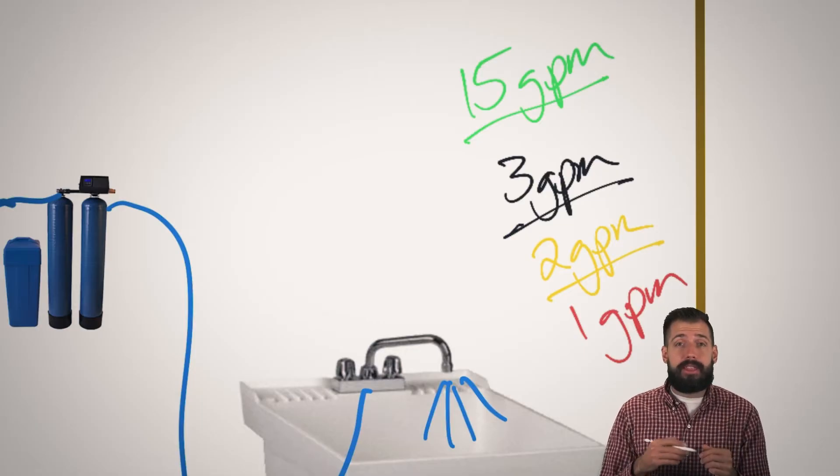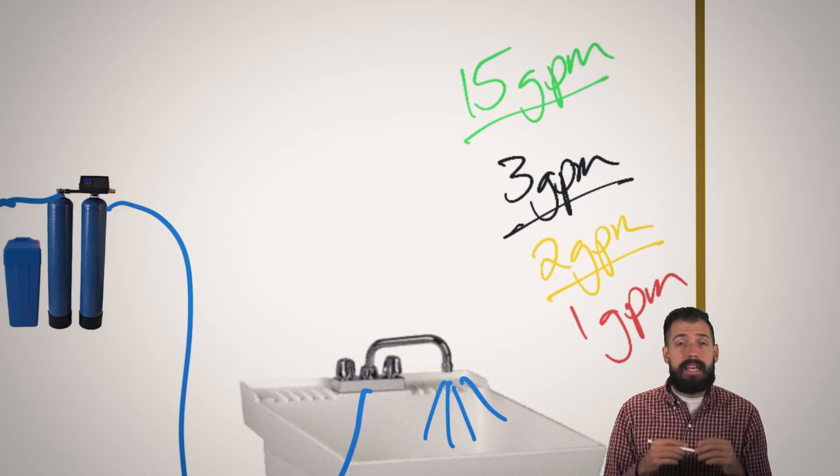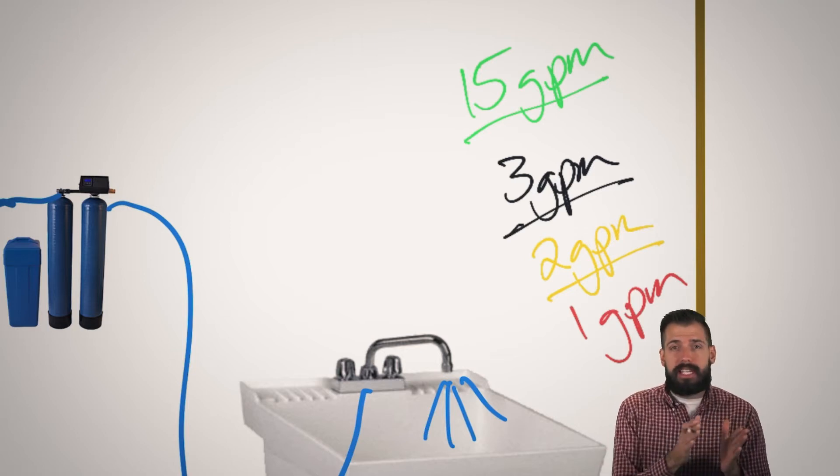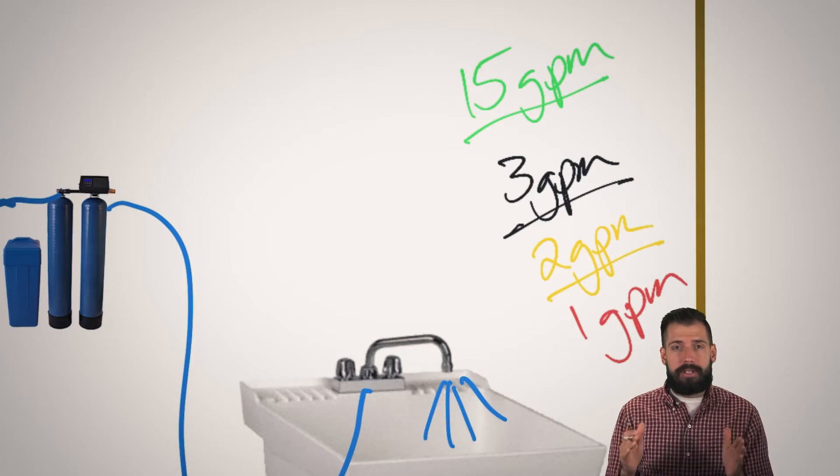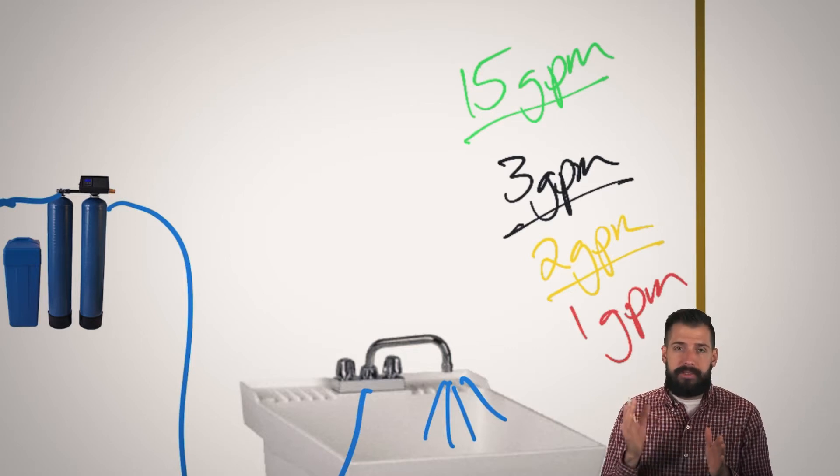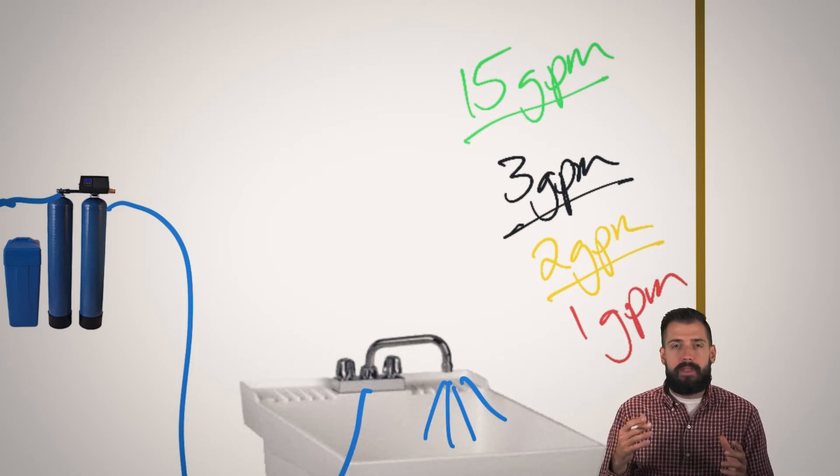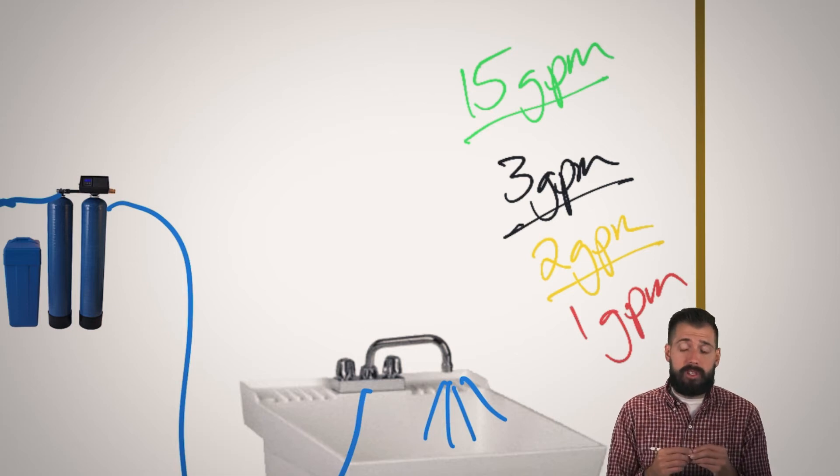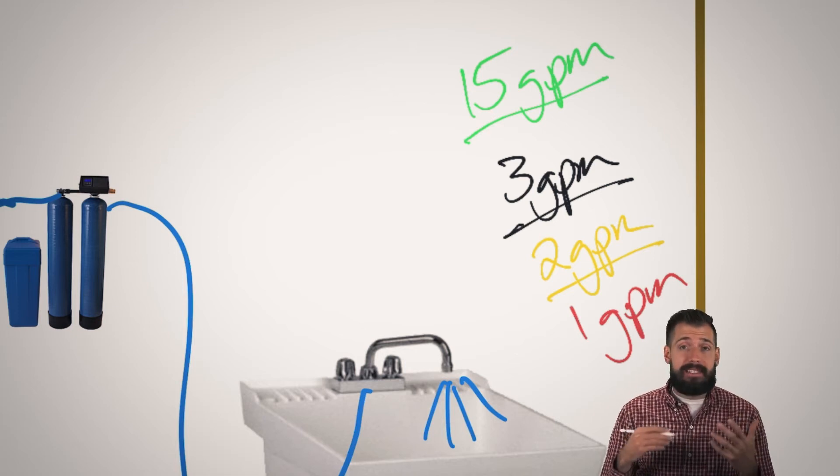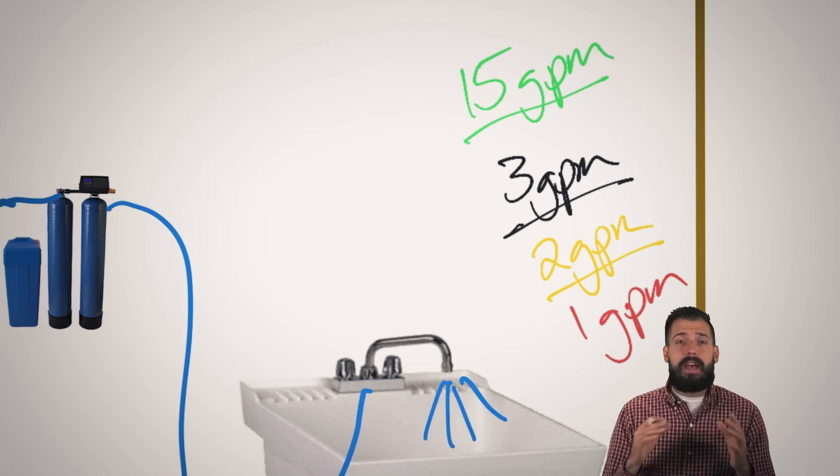Where we last left off, we were just learning that three gallons per minute is pretty ideal, but that is like the bare minimum where we want to be. And so what we did was we just ran a stress test for two hours. And at that two hour timeframe, we checked how much water was passing through. And we're constantly checking that every 15 minutes to make sure we have good flow, consistent flow. We don't have any issues. There's no air being sucked up by the well. We don't have any problems like that. So we now know that we have passed the test. Congratulations. We did two hours. We were above three gallons per minute. Everything is amazing.